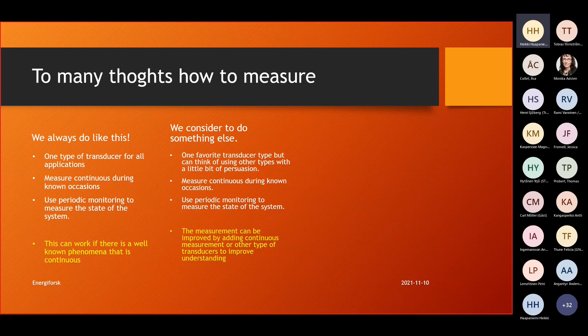You monitor continuous during known occasions - if you have a valve test or something, you perhaps have a continuous measurement during that valve test, then you take your continuous measurement away and perhaps do periodic monitoring on the same transducers during the rest of the time. Then you can learn if the occasion you measured has any impact on your system.